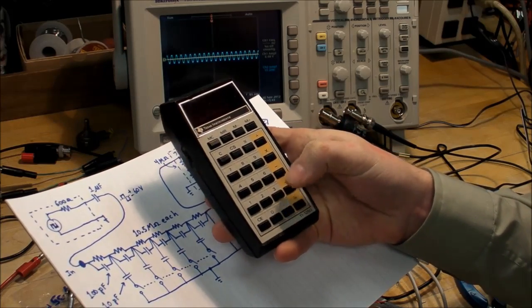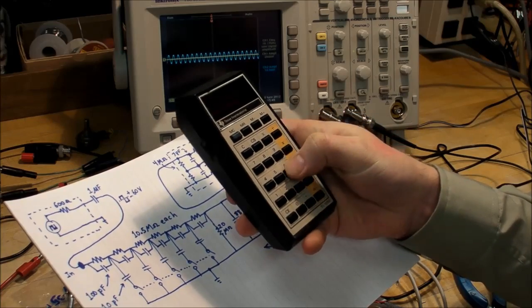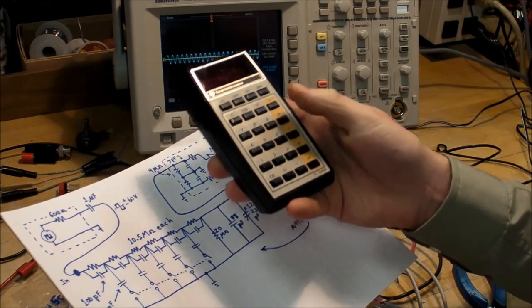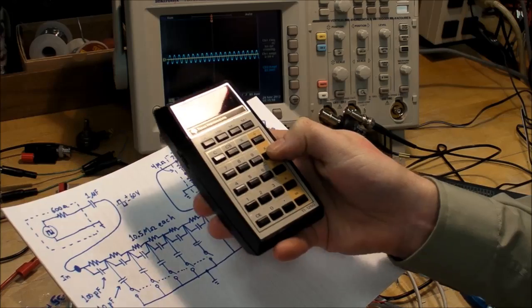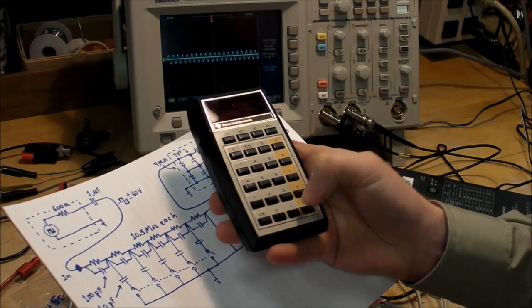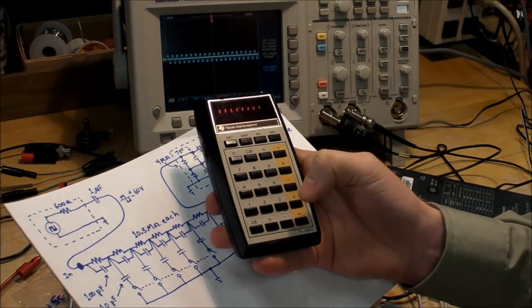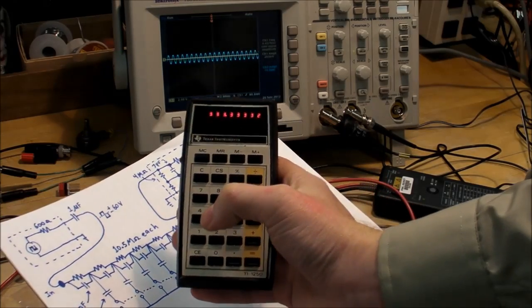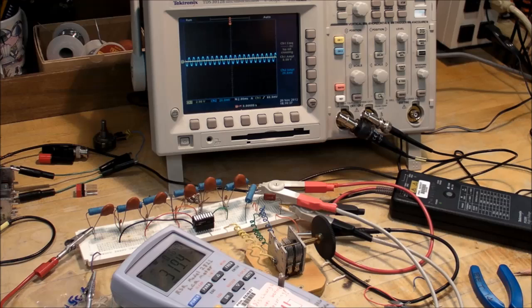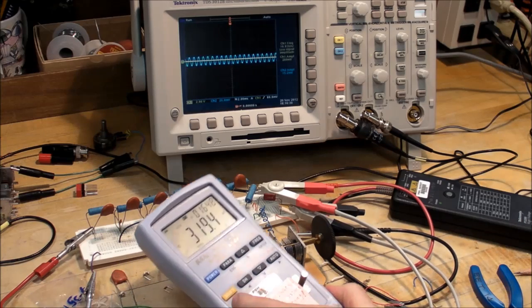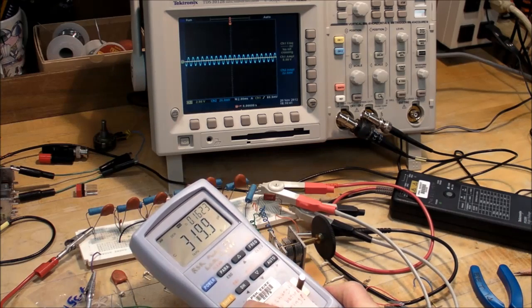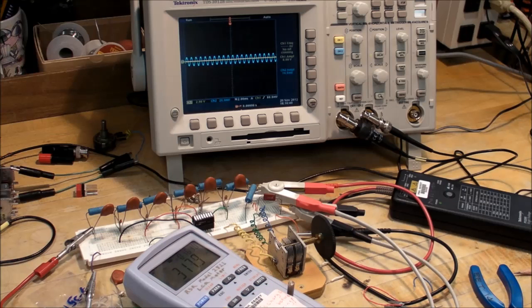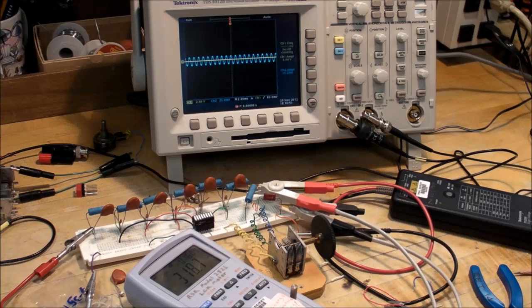Then multiply that by 20 and we get 333 picofarads. And 333 is good compared to what I'm measuring, that's about a one percent error. So I would say that this high voltage probe is definitely compensated as it is now.